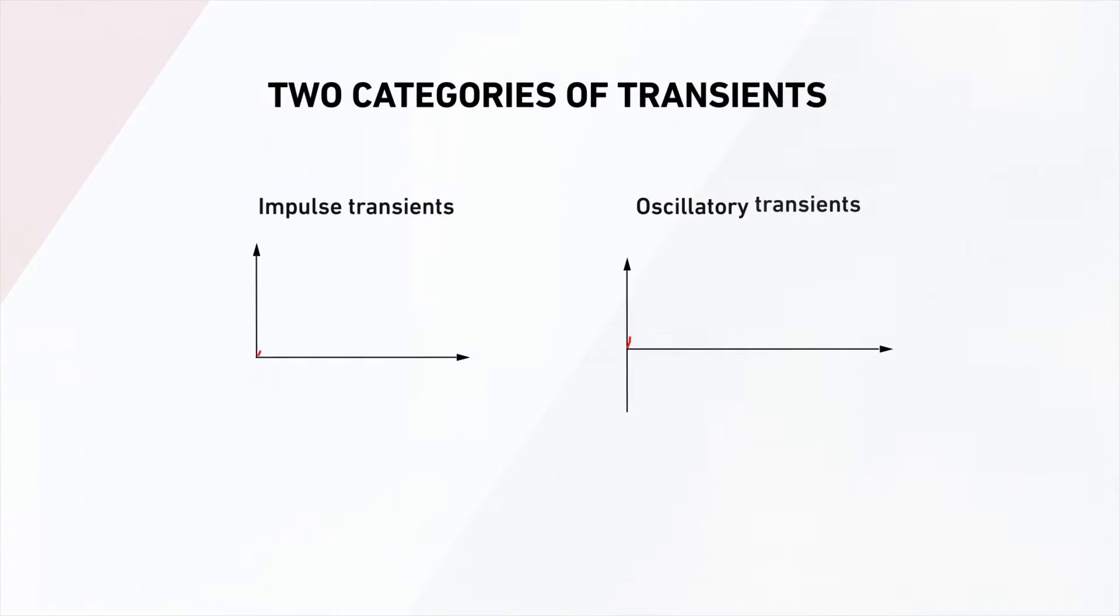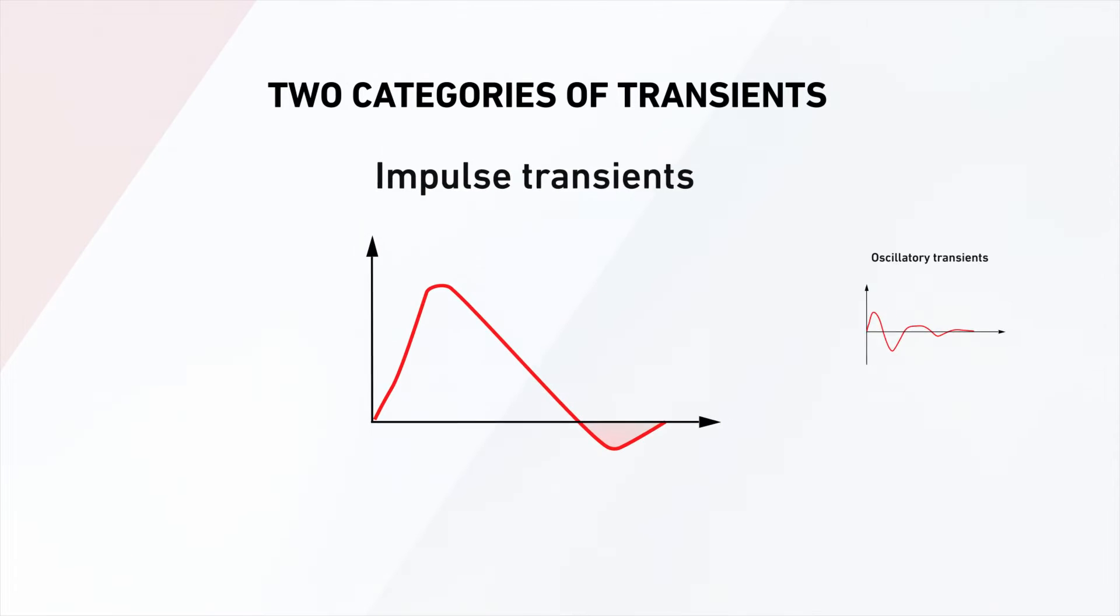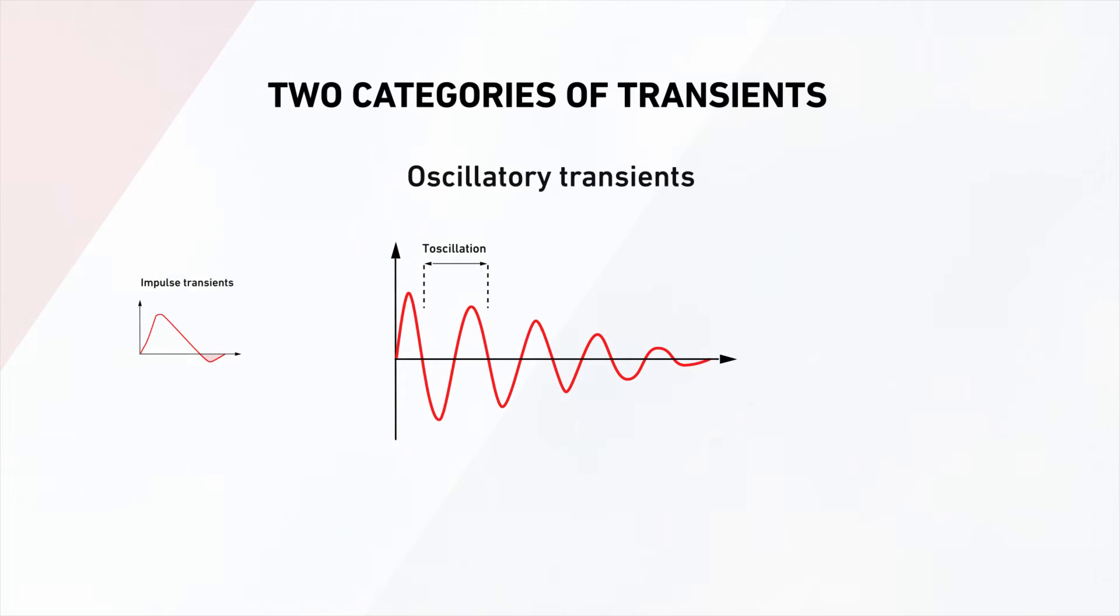Impulse and oscillatory transients are the two major categories of electrical transients. Impulse transients have the majority of the energy either in one direction or polarity, as well as a large decrease in the maximum value following the initial pulse. Oscillatory transients have a ringing component, where polarity rapidly changes as the values decay.